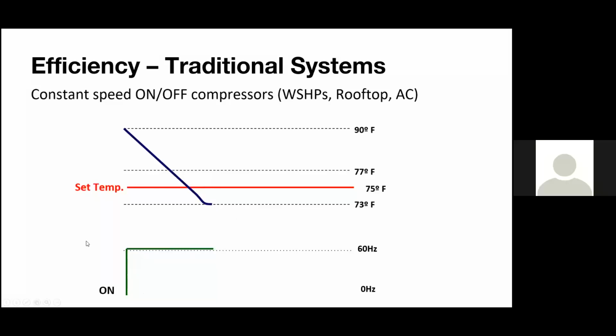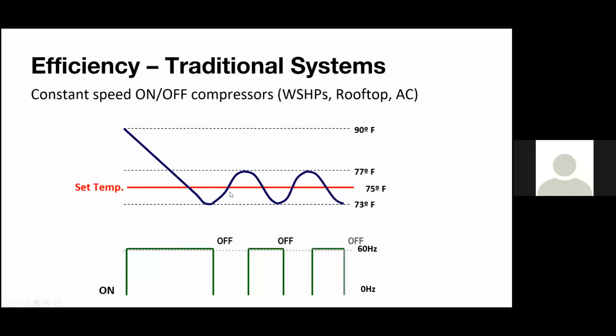And as soon as we go past that, we're going to shut off the compressor. So the compressor shuts off. What happens? The temperature rises in that space, eventually getting to 77, maybe 78. The compressor needs to turn back on, and it's going to do that on-off cycling, right? So there are a couple of takeaways to look at for this conventional system.